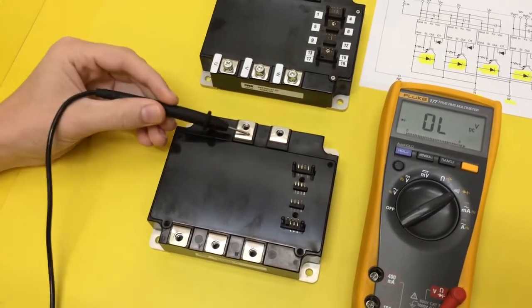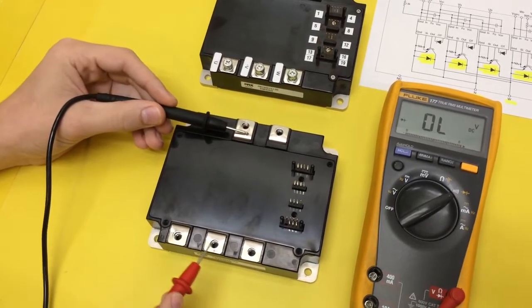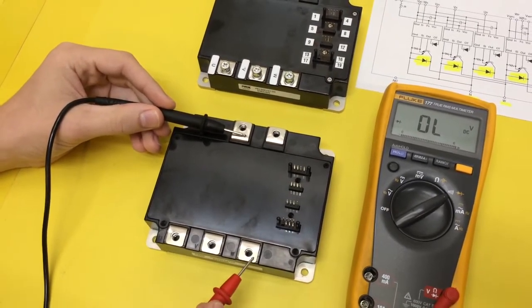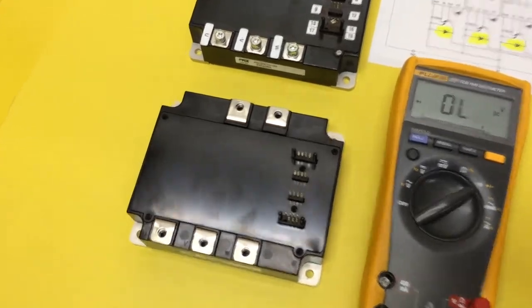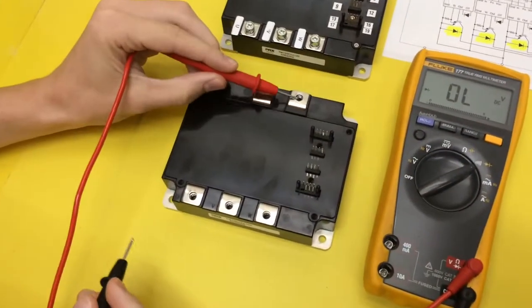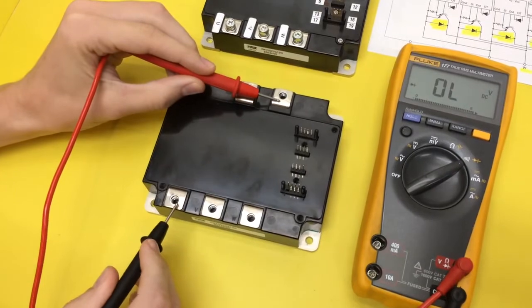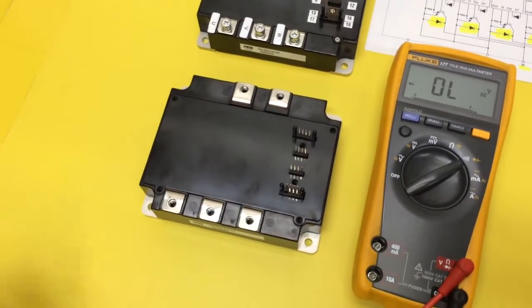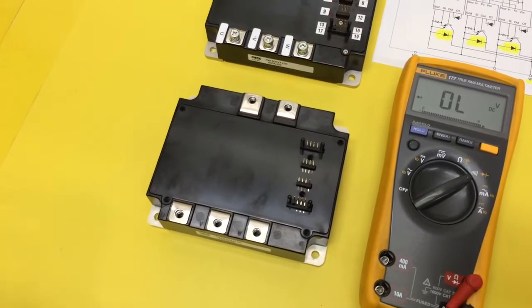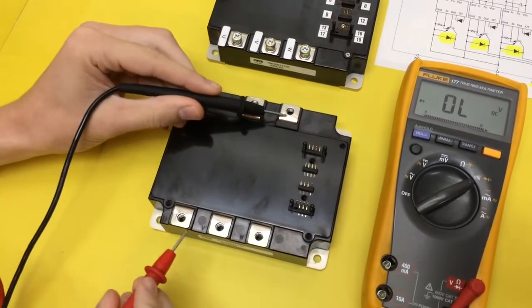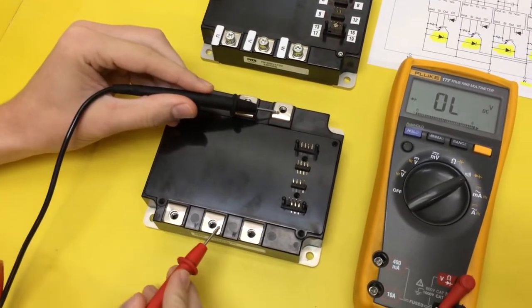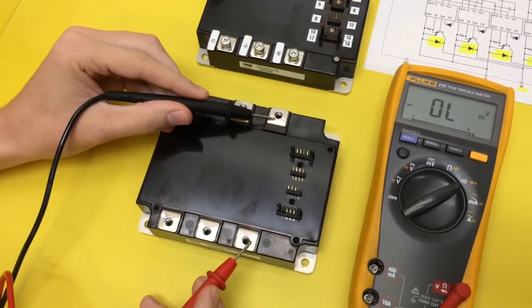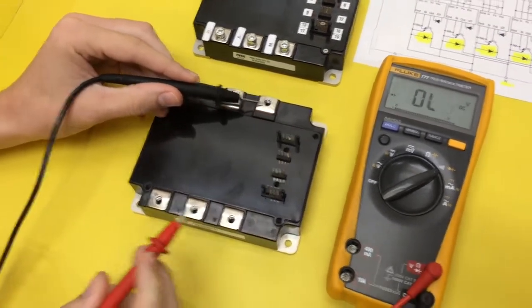He's going to swap his meter leads and do the same thing. We should read OL. Okay, now he's going to go to P positive. The way you know it should read OL is if two out of three or all three do. Now he's going to swap his meter leads again and he should read the diode drop, and he does. So nothing read unusual there.